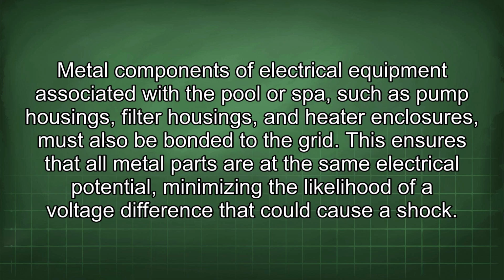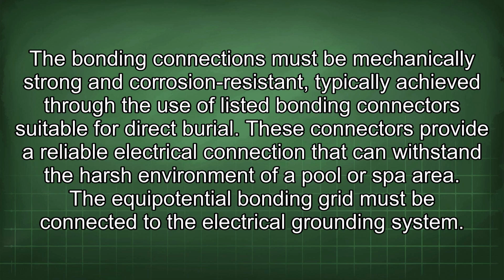Metal components of electrical equipment associated with the pool or spa, such as pump housings, filter housings, and heater enclosures, must also be bonded to the grid. This ensures that all metal parts are at the same electrical potential, minimizing the likelihood of a voltage difference that could cause a shock. The bonding connections must be mechanically strong and corrosion resistant, typically achieved through the use of listed bonding connectors suitable for direct burial. These connectors provide a reliable electrical connection that can withstand the harsh environment of a pool or spa area.